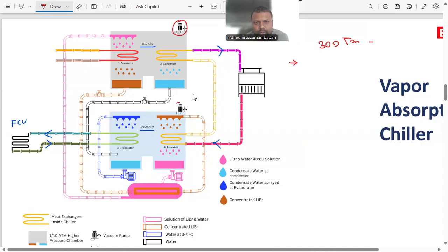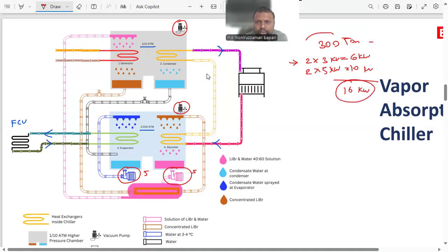We have two vacuum pumps. So two vacuum pumps will be individually around, let's say, 3 kilowatt, together 6 kilowatt. And there are two pumps here. The pumps are individually around 5 kilowatt. So 2 into 5 kilowatt will be 10 kilowatt. So 16 kilowatt is the electrical energy you need basically to run the whole 300 TR. Highly efficient, isn't it? However, the biggest challenge and also the beauty of having this chiller is the generation of hot water.